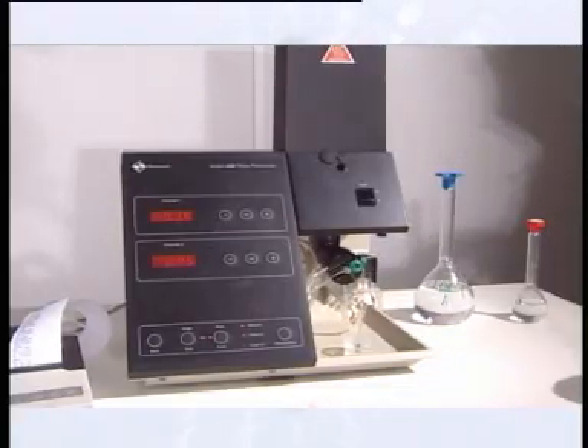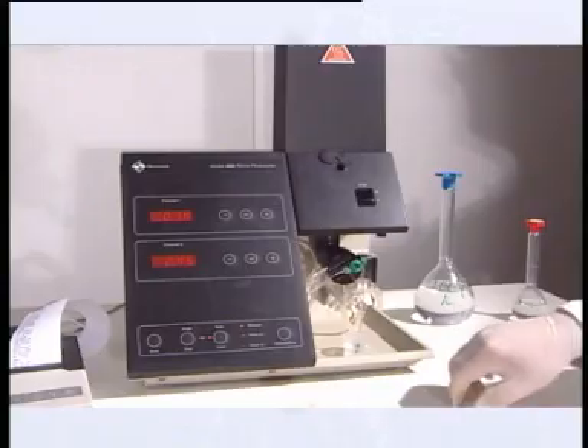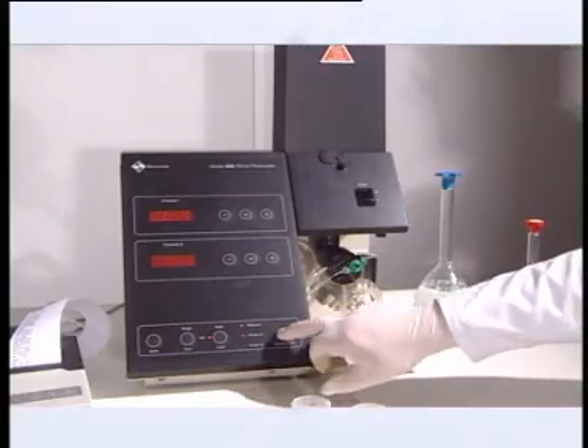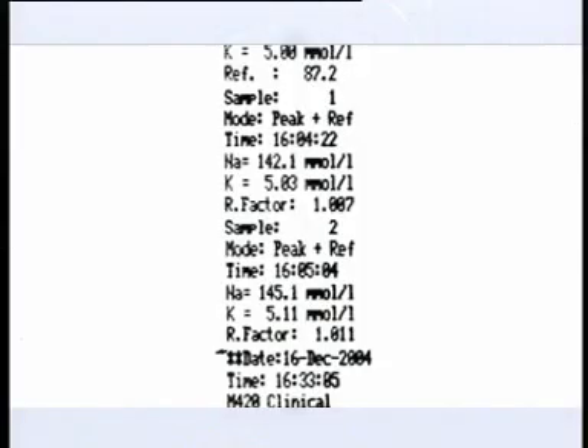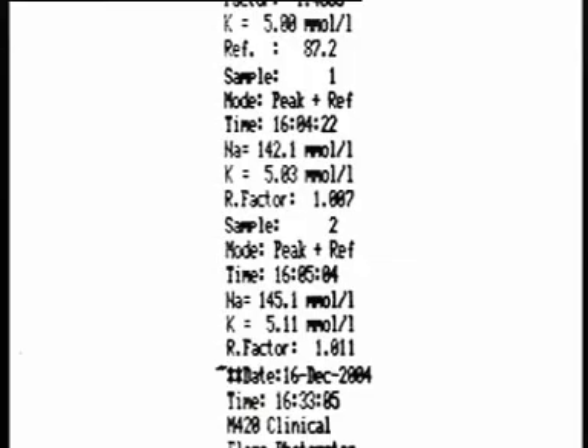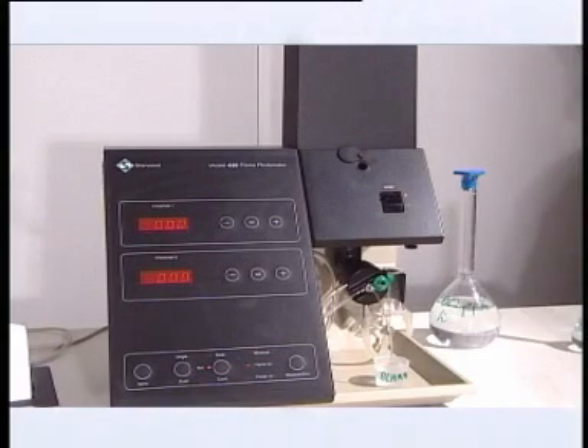The sample is aspirated and the measure button pressed. After 20 to 30 seconds, the sample value is captured and the value printed. Also printed is the relative lithium value, which shows the drift from the calibration value of 1.000. This drift has been compensated. The Model 420 numbers measured samples in sequence 1, 2, etc.